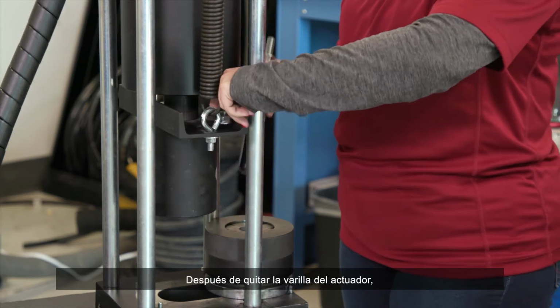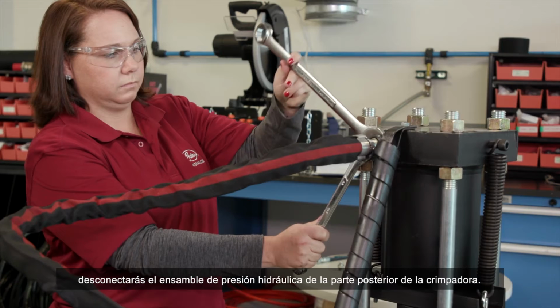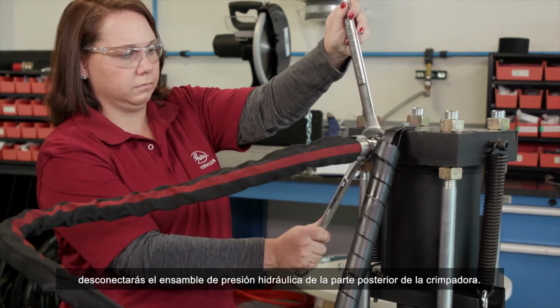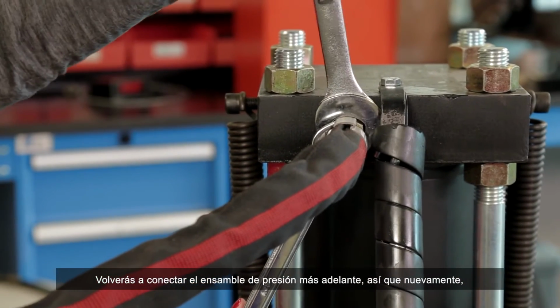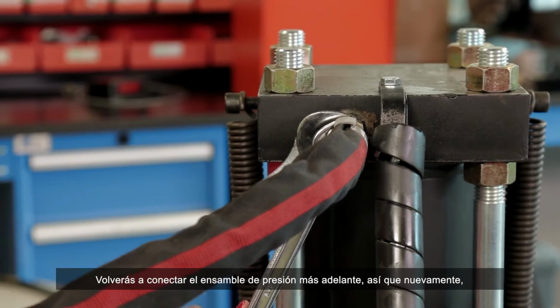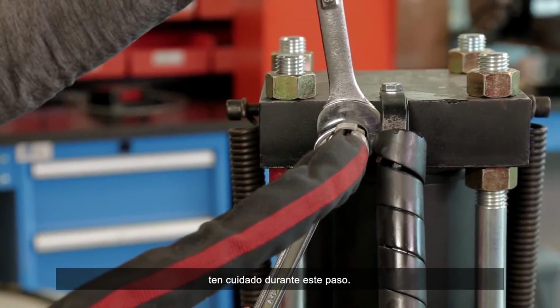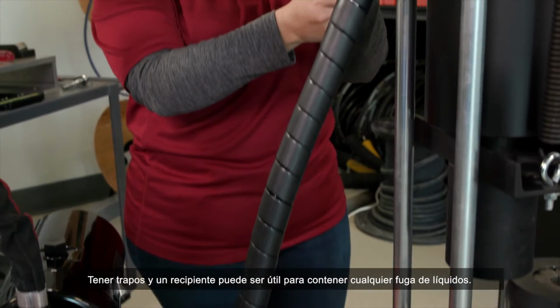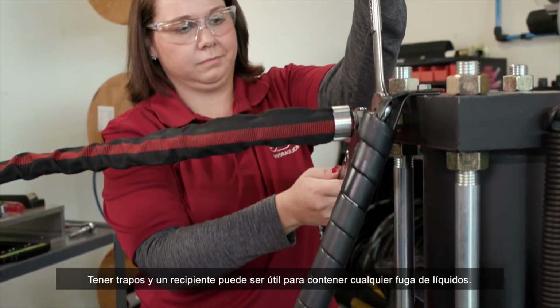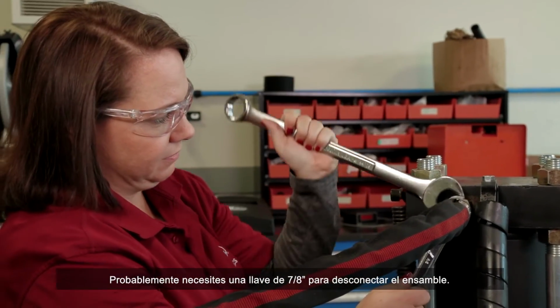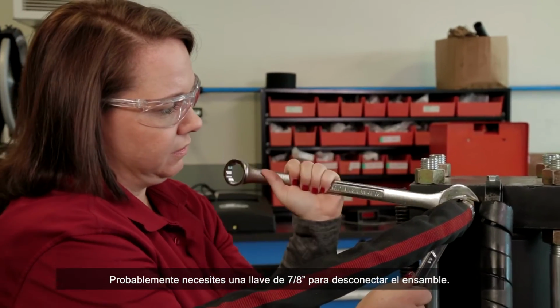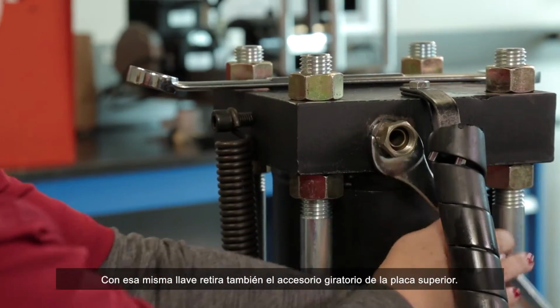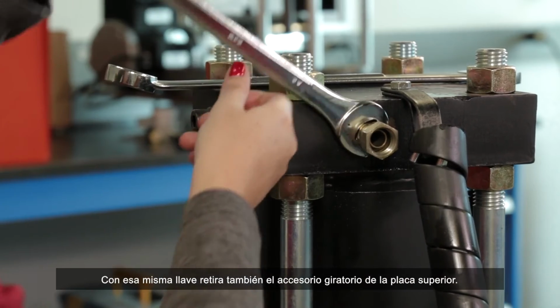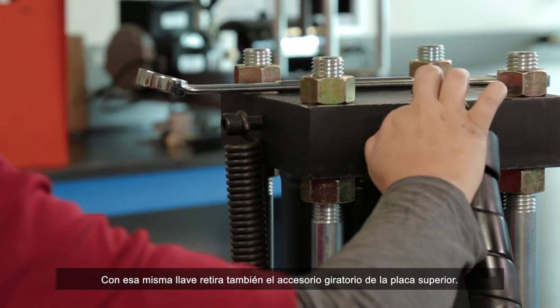After removing the actuator rod, you'll disconnect the pressure line from the back of the crimper. You'll be reconnecting the pressure line in a later step, so again, use caution during this step. Rags and a basin are handy for catching any fluid leakage. You will likely need a 7/8 inch wrench to disconnect the pressure line. With that same wrench, also remove the swivel fitting from the top plate.